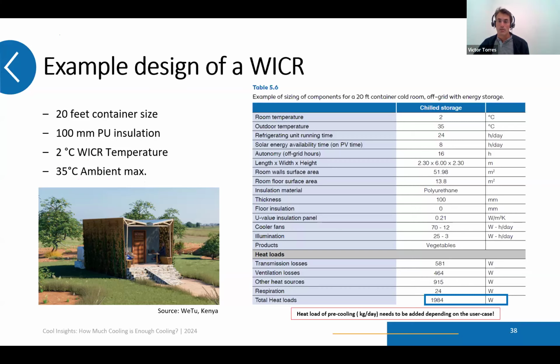In this table you can find all details of the cold room analyzed, and here you see the heat loads — the calculation of cooling demand divided into different factors considered: transmission losses, the thermal loss through the walls, air infiltration, respiration, and so on. We arrive at a maximum cooling demand of about 1,900 watts, which we'll take as the reference for our calculation.